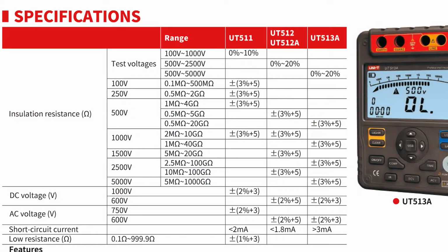or repair. There are three slightly different models available from UNI-T: the UT-511, 512 and 513. In the specs you can see the main differences of the three available models. Only the UT-511 starts with 100 volts and the two others with 500 volts. The maximum and minimum resistance values you can measure depends on the different test voltages.